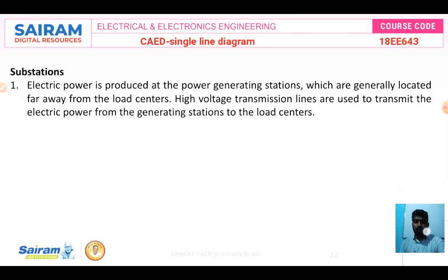So see your substation. First we'll go to substation. What are substations practically? A substation is a station which gives power supply to the consumer, from 11 kilovolts to 415 volts three phase or 230 volts single phase. Keep it in your mind, the single phase supply we are getting from the power supplier is 230 volts plus or minus 6% tolerance, not exactly 230 volts or 220 volts. We'll get 230 plus or minus 6%, that is 218 to 242, right?